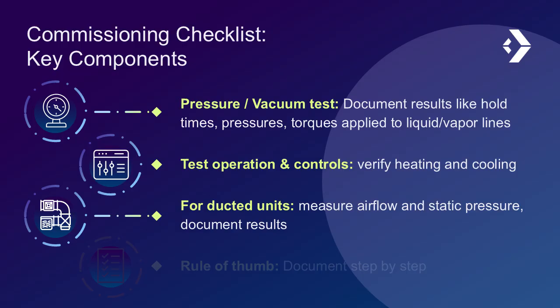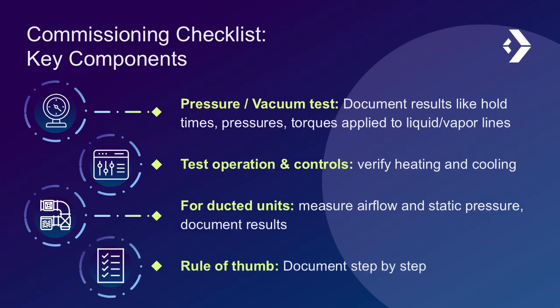For ducted units, measure airflow and static pressure. Document those results, and confirm that the ducts are properly sealed. Basically, you're documenting step by step that the heat pump is ready to go. Consistent use of a commissioning process and checklist will lead to better performance, fewer callbacks, and better consistency across your install team.